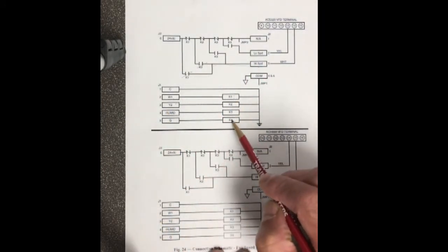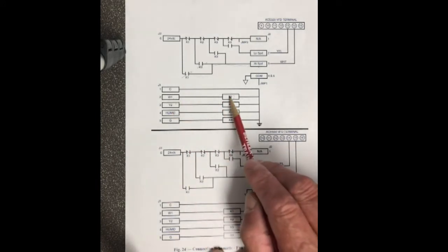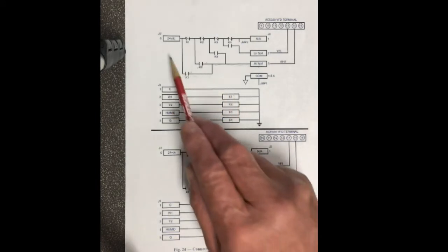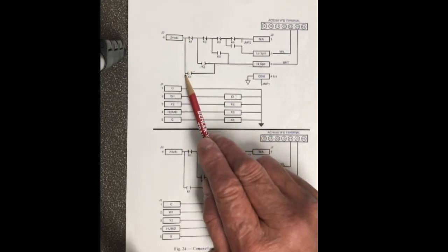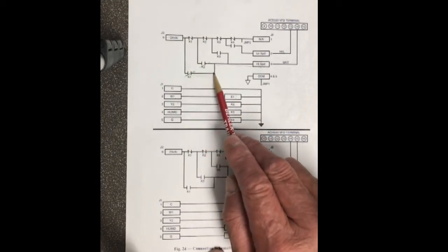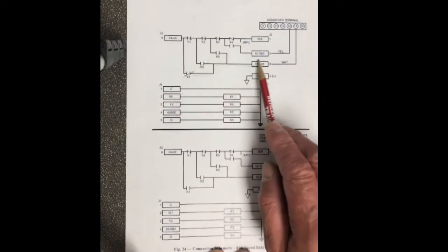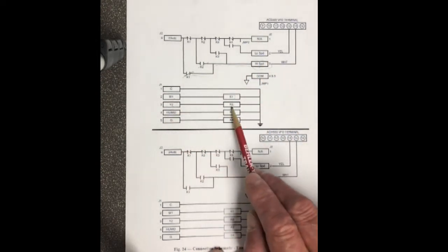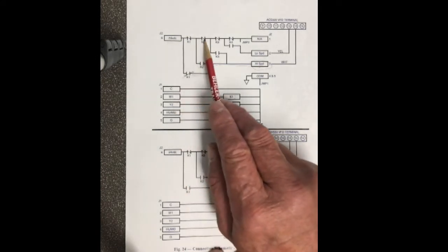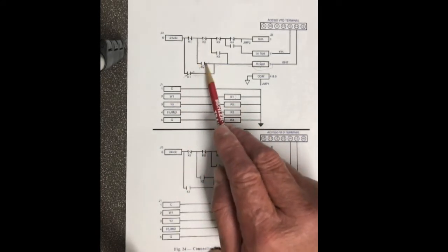So on a call for W1, it energizes K1. If I look through here, 24 volts DC is going to come down here when this is closed, K1. I'm going to come through here, I'm going to energize a high speed setting. Y2, K2. So if I follow K2 across, we're going to see K2 is going to close. We're also going to go to high speed.